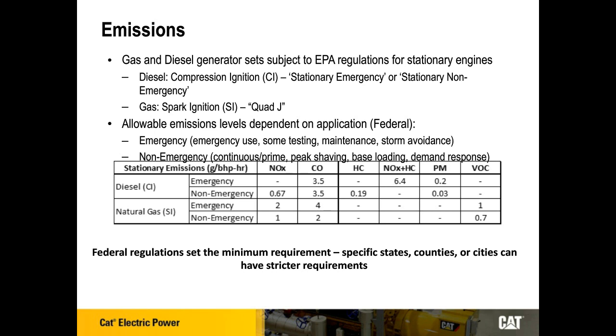So that's the regulation, and there are also different emission requirements for the application. At the federal level in North America, you have both emergency and non-emergency product. On the emergency side, this is for when there's a loss of utility, as Bailey talked about earlier—you can do testing, maintenance, and storm avoidance under this emergency application. When you go to your non-emergency product, that's when you're using the engine while you still have utility, so using it in a continuous or prime application, peak shaving at a facility, base loading, and demand response. So you have different classifications for diesel and gas, and also different requirements based on how you're actually using that generator set.